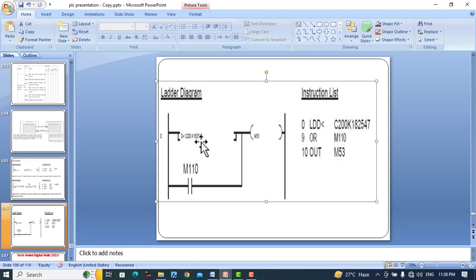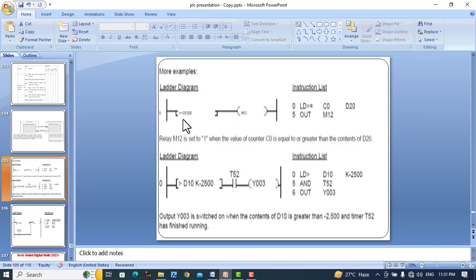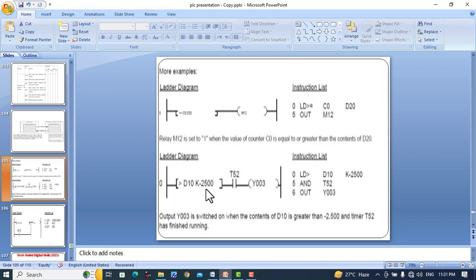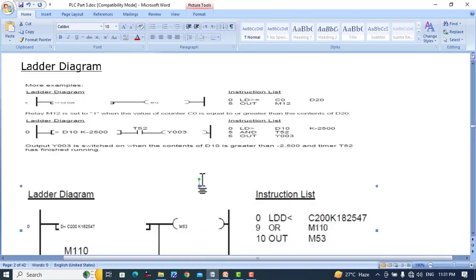Another example: >= C0 D20 will compare counter value C0 with D20, and when C0 is greater than or equal to D20, the output relay will be turned on. For > D10 K2500, when the value of the 16-bit data register D10 is greater than the numerical value 2500 and timer T52 has also finished running, then output Y3 will be switched on. Output Y3 is switched on when the content of D10 is greater than 2500 and timer T52 has finished.